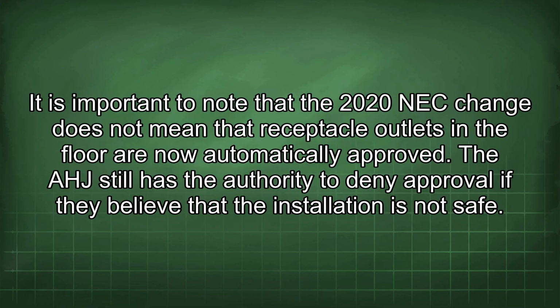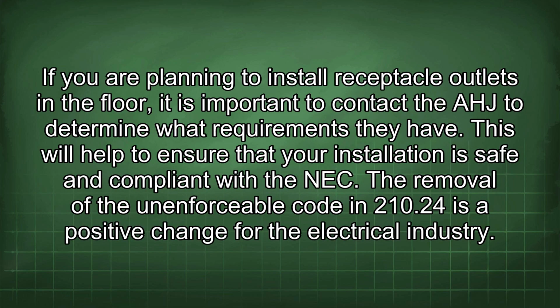It is important to note that the 2020 NEC change does not mean that receptacle outlets in the floor are now automatically approved. The AHJ still has the authority to deny approval if they believe that the installation is not safe. If you are planning to install receptacle outlets in the floor, it is important to contact the AHJ to determine what requirements they have. This will help to ensure that your installation is safe and compliant with the NEC.